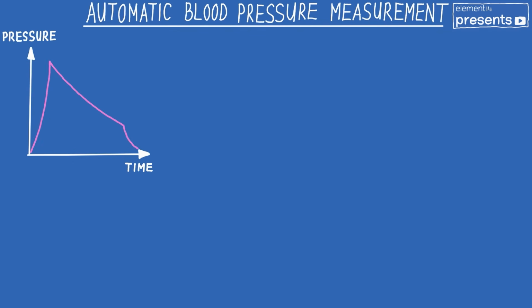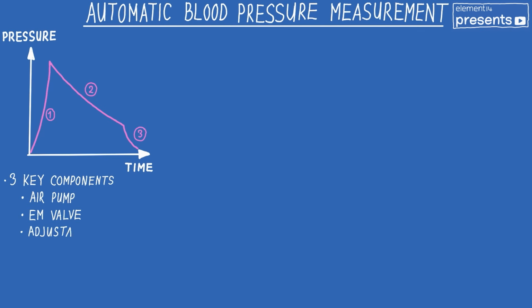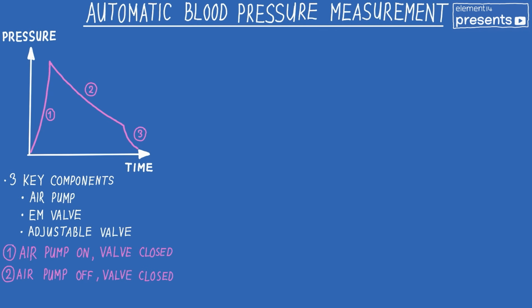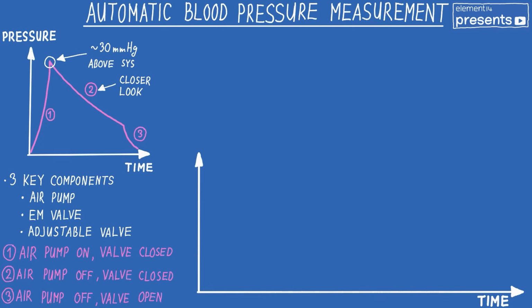So we can differentiate three different parts in measuring the pressure. There are three active components, two of which we control, which are the air pump and the electromagnetic valve, and there is an adjustable valve which lets out the air the whole time during the measurement. In the first segment, we are pumping up the arm cuff, so the air pump is on and the valve is closed. In the second segment is where we actually do the measurement. The pump is off and the valve is still closed, but only the adjustable valve is letting air out. And in the third segment, we just let the air out with the valve. So the blood pressure monitor actually pumps up around 30 millimeters Hg above the systolic pressure, so it does a rough estimation when it's pumping up the arm cuff.